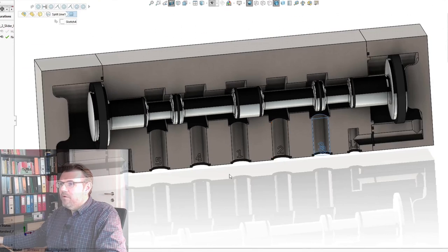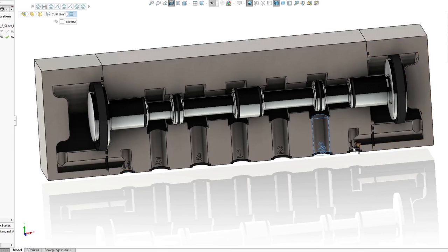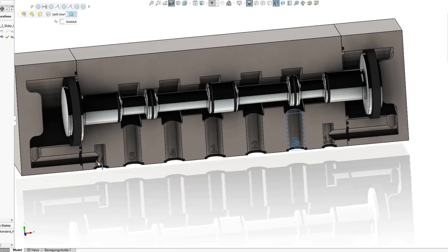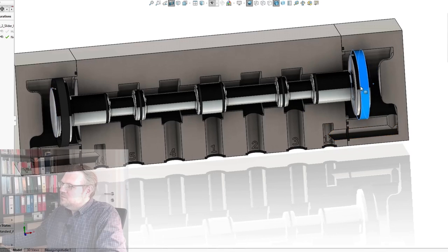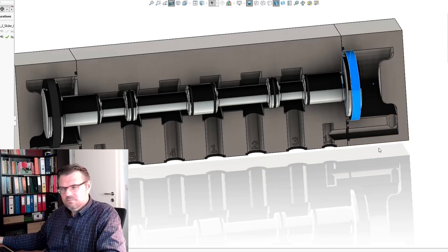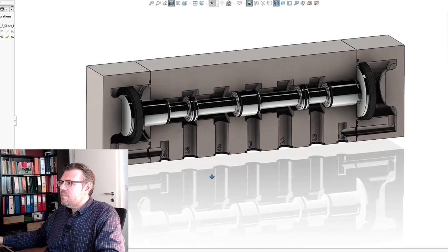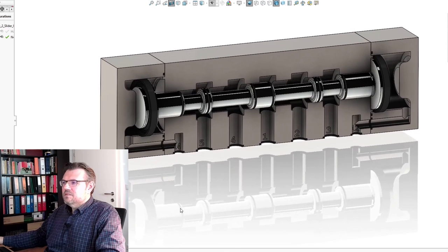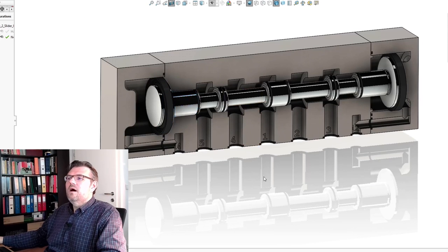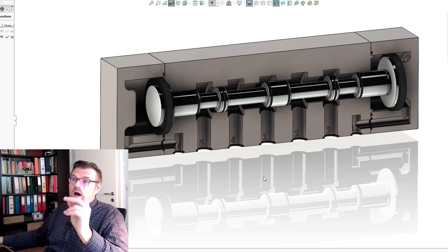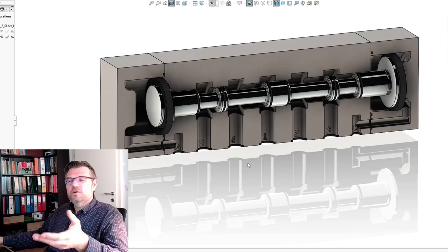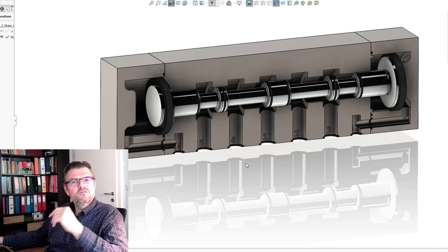And how is it operated? Well, there is the 1-4 pressure line and there's the 1-2 pressure line. If we apply pressure here at the 1-4 line, this will be moved in this direction with this piston here. And if we apply pressure here at the 1-2 line, this will be moved in this direction with this piston here. So these are the two pistons. So actually, this is how this looks like. One position, other position, and now what could happen is that you don't have pressure and you want to bring this valve into a certain position.